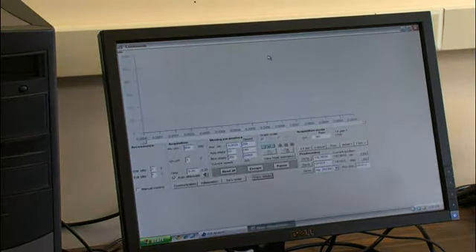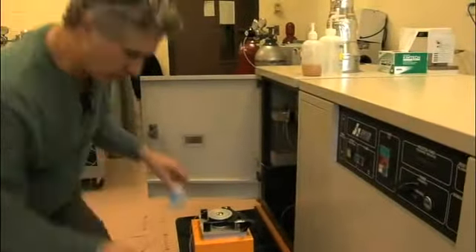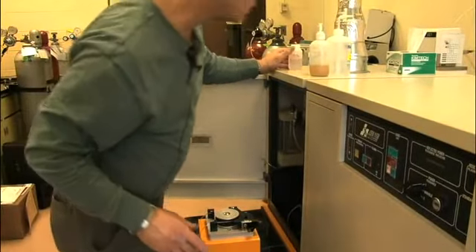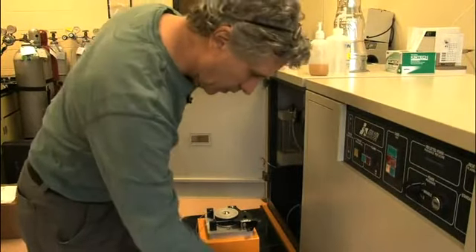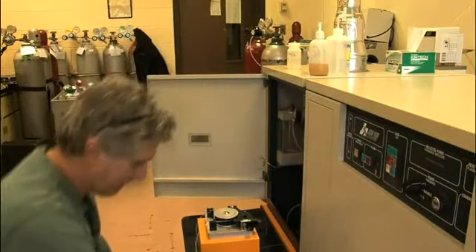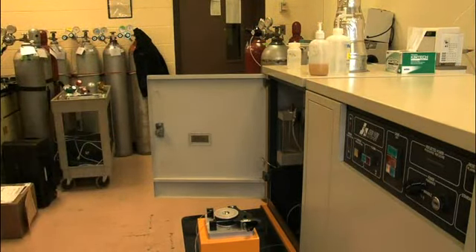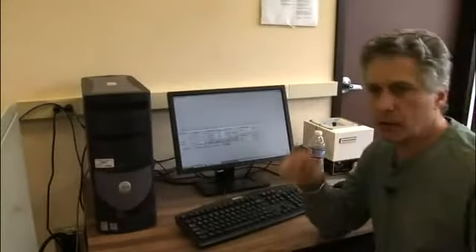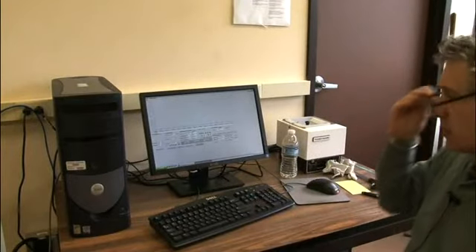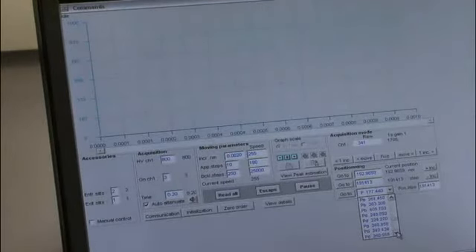What this does is allow you to control the grating and the slits manually. What I'm going to do is put in a standard that we have made. That standard has aluminum, lead, cadmium, potassium, magnesium. So I'm going to go manually to a lead peak. Here I choose what element I want, and I'm going to go to the most sensitive lead line. It's 220.353. Click on go.